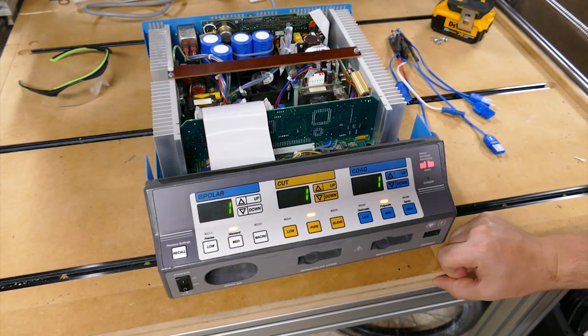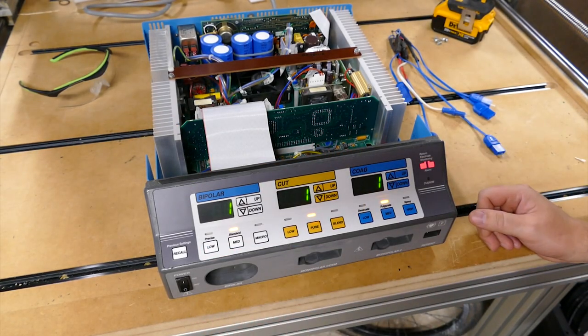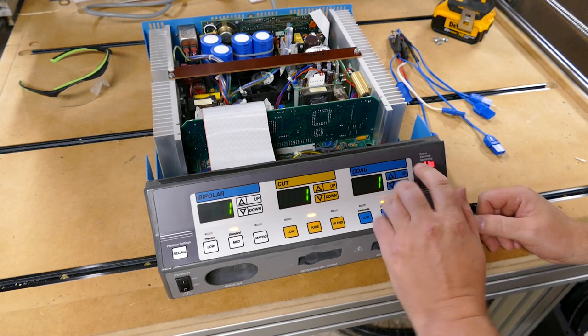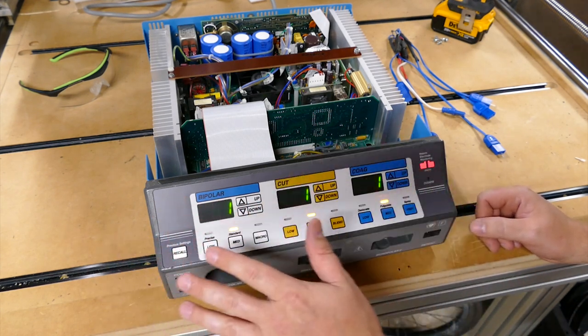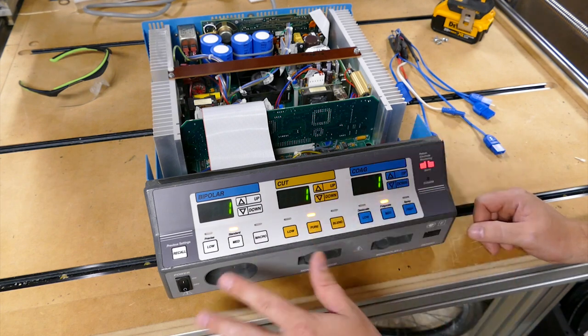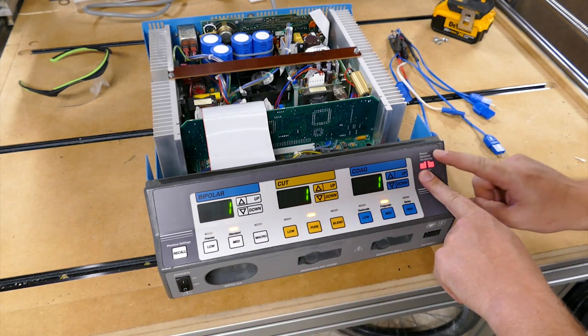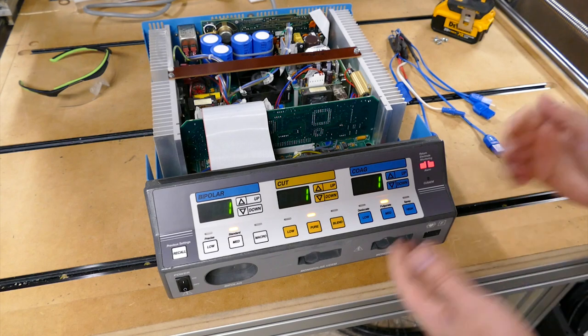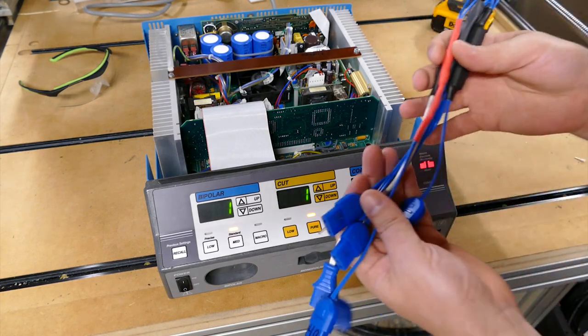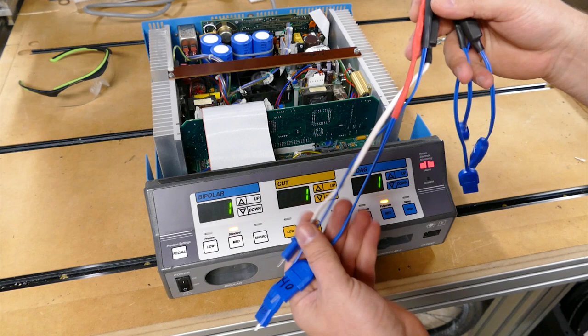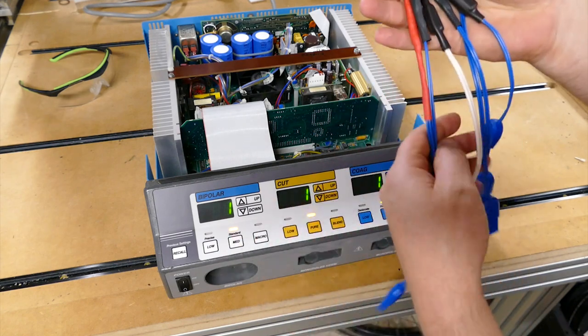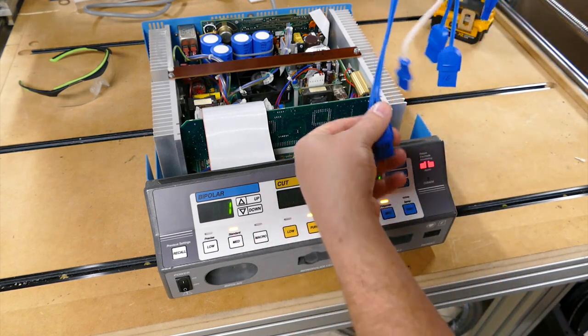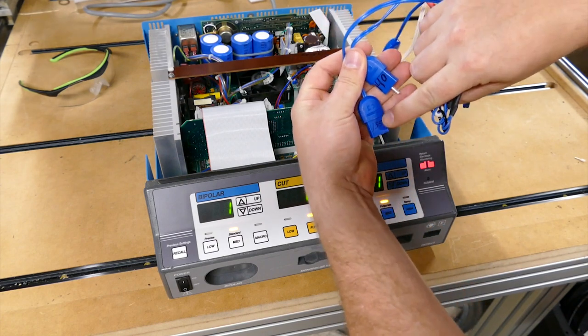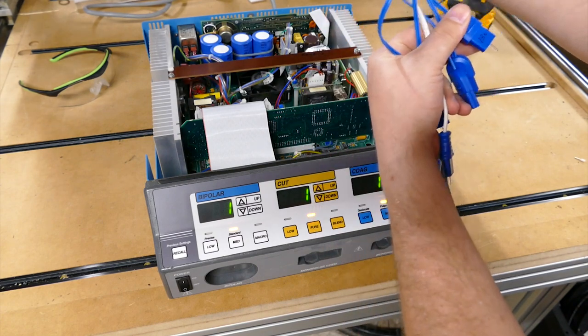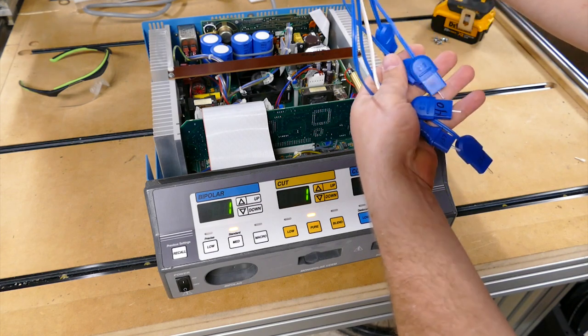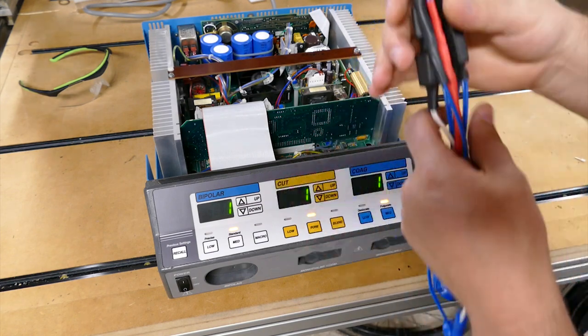So what is going on with this beautiful piece of history? Well, this guy right here. All the rest of this will probably be just fine, never give you problems, almost never need calibrating, but your return electrode monitoring can give you issues. If you look here, I've got a set of calibration keys that we made here in the shop. Some of them are verification keys. You can see I have 140 ohms, 135, I've got 130, 70, 10. But anyway, we'll get into that later.